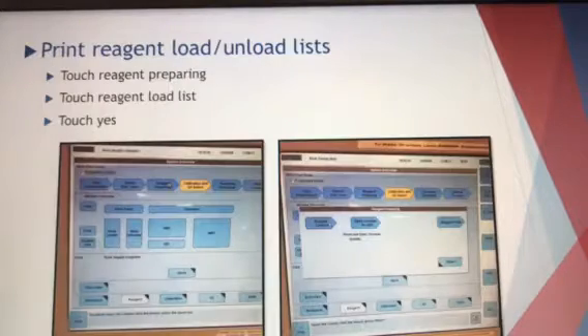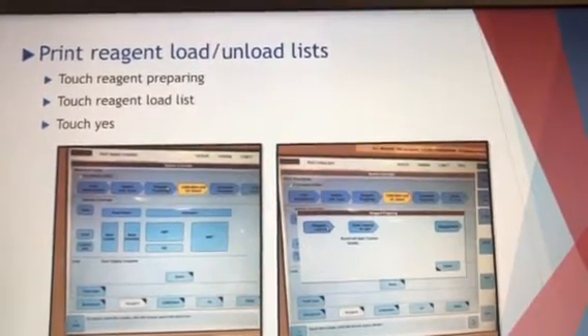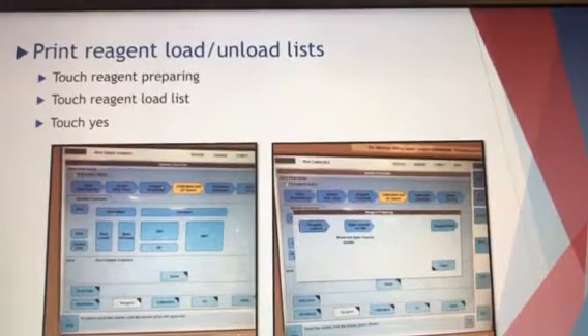So once you do that, you're going to go ahead and print your reagent load and unload list. This is a really good guideline once you check it over for yourself. Because again, you want to use your best judgment. Sometimes the analyzer will print out something that is a test we don't do a lot of, but it's telling you to replace it. So again, just use your best judgment. We'll go to that first home screen there. You're going to select reagent preparing, and then that second screen is going to come up, and you're going to touch reagent load list, and select yes, and then it'll print you out a list and tell you what to take off and what to put on. Just compare what you had written down with what the computer printed off for you.